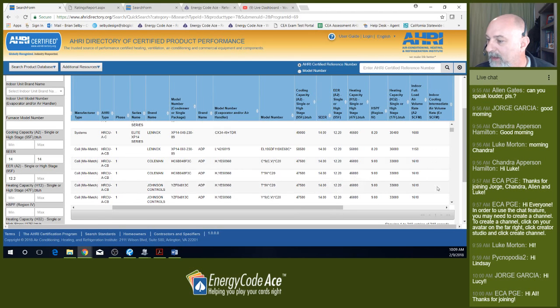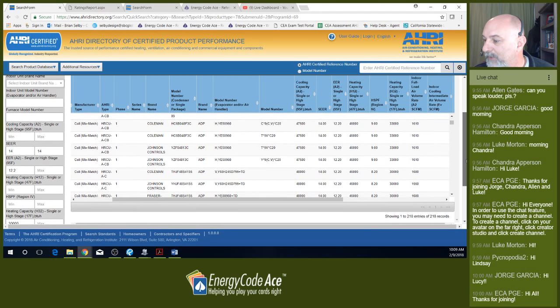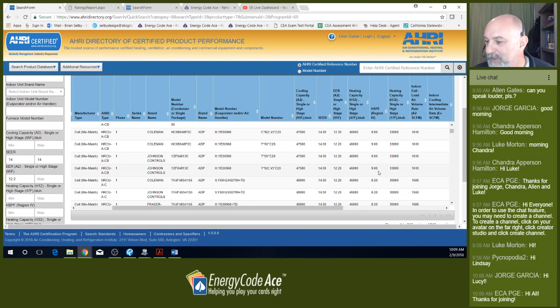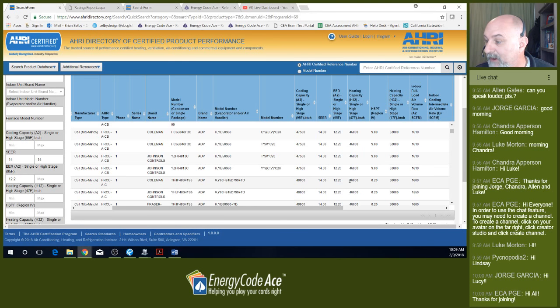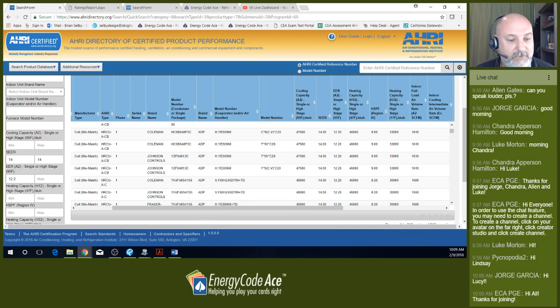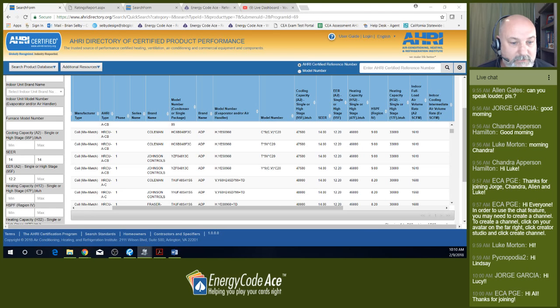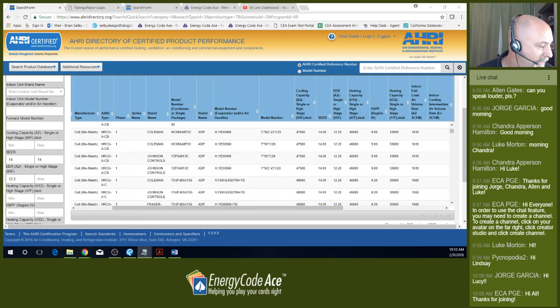Our search returned 218 records. We found a system with 48,000 BTUs cooling capacity, 14 SEER, 12.2 EER — good. The 47-degree high heat value is 46,000 BTUs. We're right at our 8.2 HSPF, and heating capacity at 17 degrees is 30,000 BTUs — perfect. So we'll enter 46,000 BTUs for the total output and 30,000 BTUs for the 17-degree heat, then switch back to the Energy Pro screen.